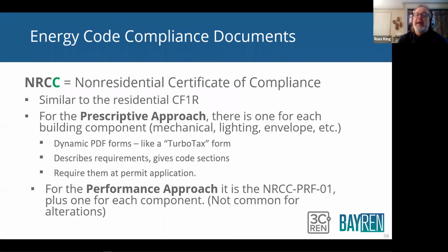So the first one is the NRCC. If you go back to that diagram, the process flow chart, what's that first step? Figure out what you're supposed to do. The NRCC is kind of like, if you're familiar with the residential side of the energy code, there's something called the CF1R. The NRCC is sort of the non-residential version of the CF1R. It tells you what you're supposed to do, all right? For the prescriptive approach, there is one NRCC for each building component. So there should be one for mechanical, one for lighting, and one for envelope.